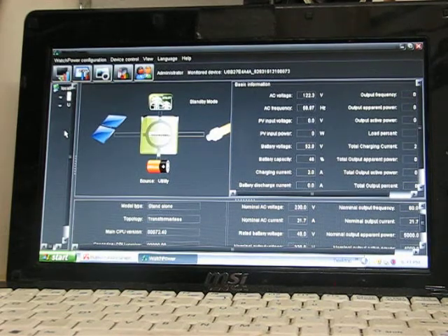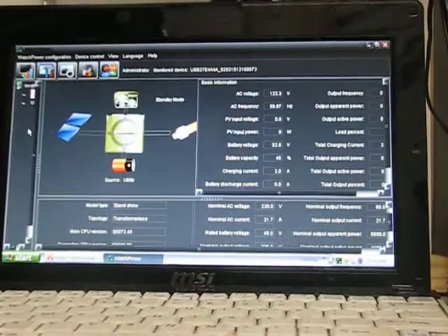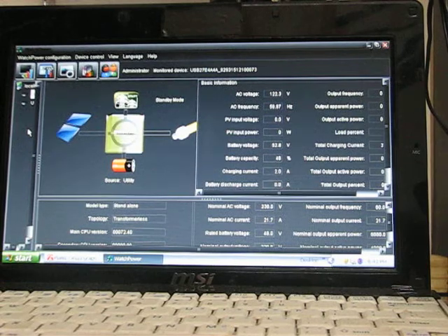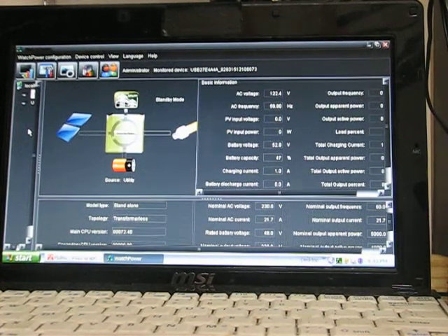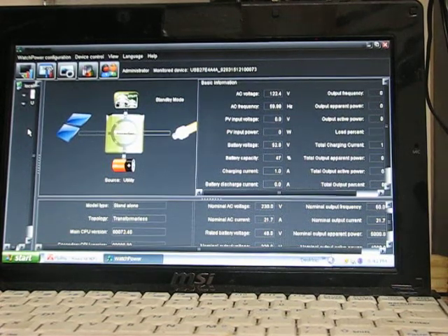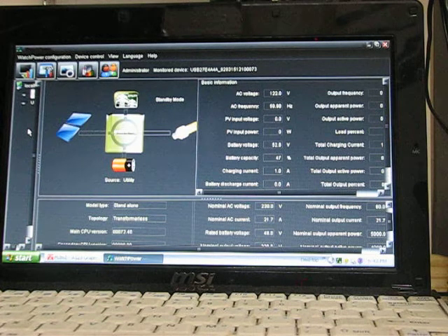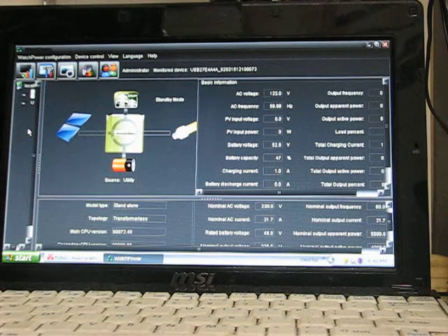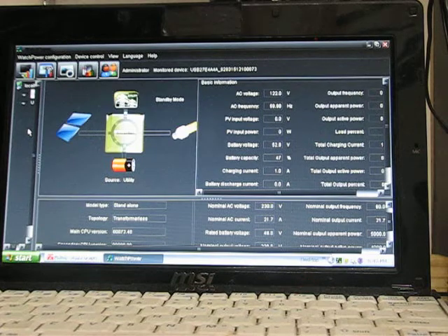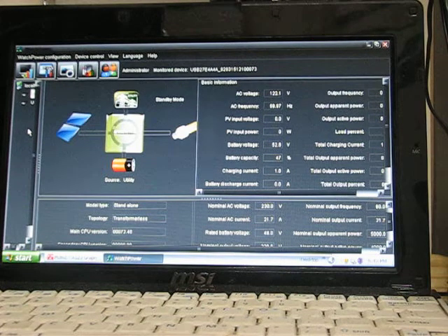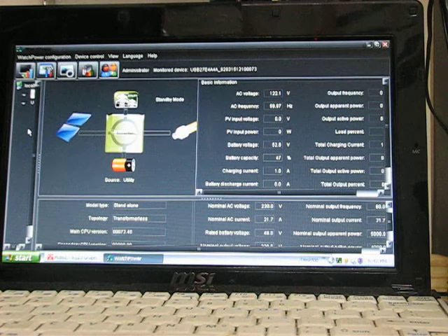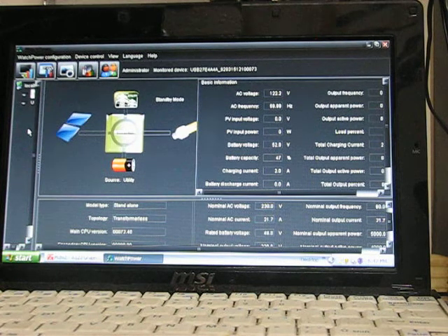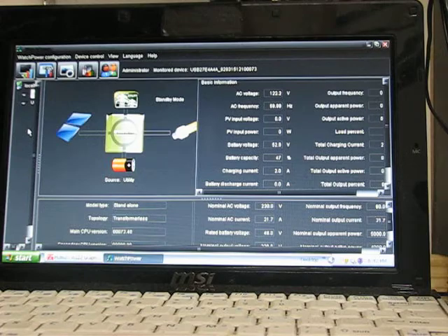I have it set on the timers to come on at, the inverters come on at 6 a.m. And the grid switch over is 6:05. So I think that'll help the inverters last rather than just getting hit with a load, being able to sit at idle for five minutes. And then the same thing when they switch off. I have the grid come on and let the inverters sit on for an extra five minutes before they switch off.